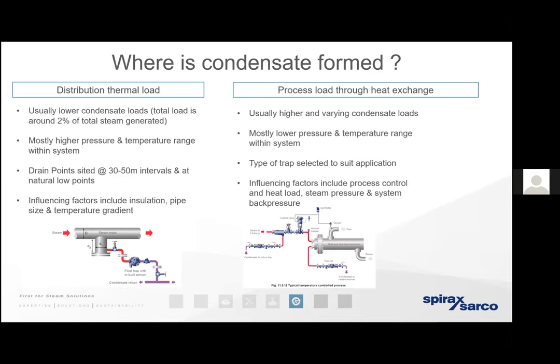For example, if we're generating 10,000 kilograms per hour of steam, we'd expect a running load condensate mass of 200 kilograms per hour. We double that to 400 kilograms per hour to allow for the warming-up load. If we fail to account for that increased mass when sizing steam traps and the condensate return infrastructure, there's a risk the condensate could be held back ahead of the steam trap, backing up and slowly flooding the distribution pipework — increasing exposure to erosion, corrosion, and water hammer.